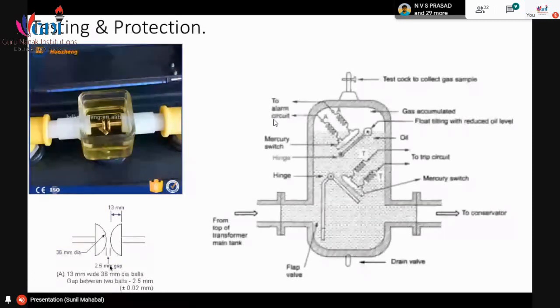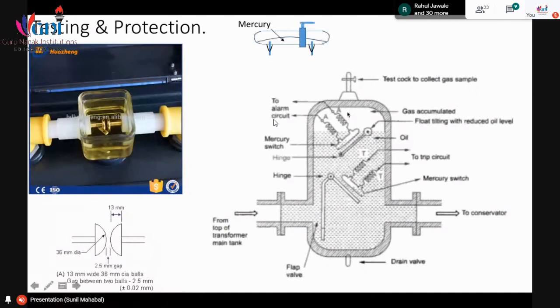Then on the right side, you can see the Buchholz relay, and there are mercury switches inside it. Mercury switches work on the gravity principle, and this is how it works. On the top, you can see the mercury switch. There are two probes, and there is mercury here. The mercury is shorting the two probes, so there is a short between these two probes. So it is an NC contact, a normally closed contact.